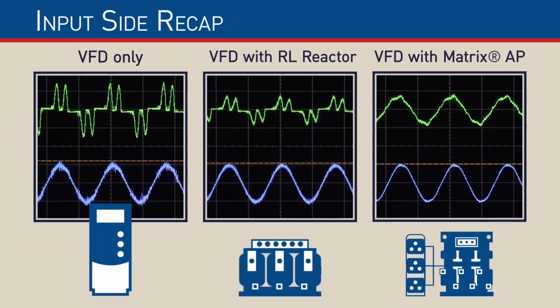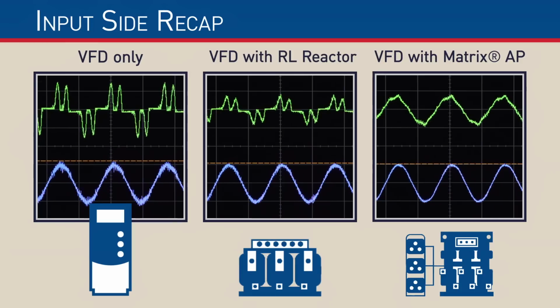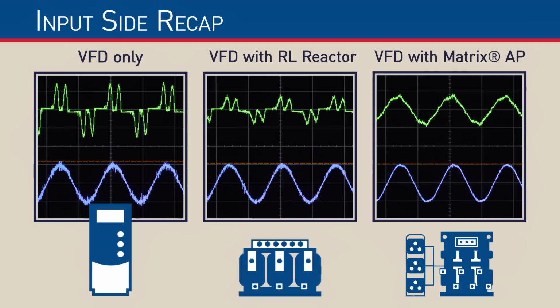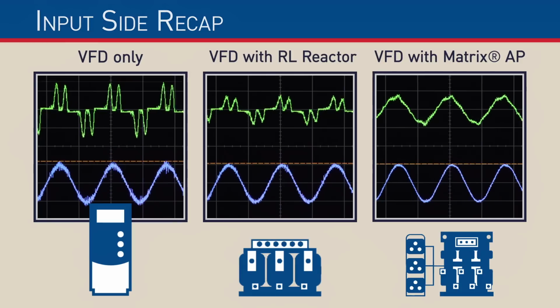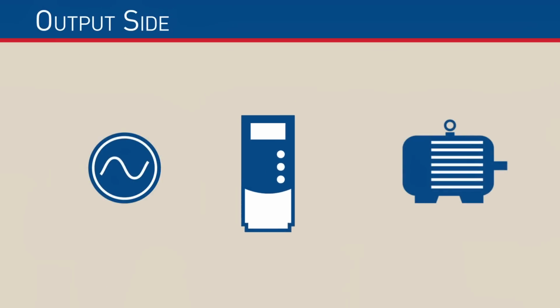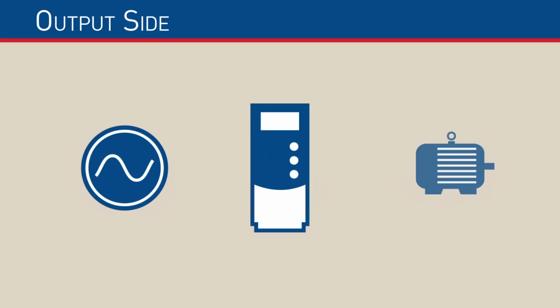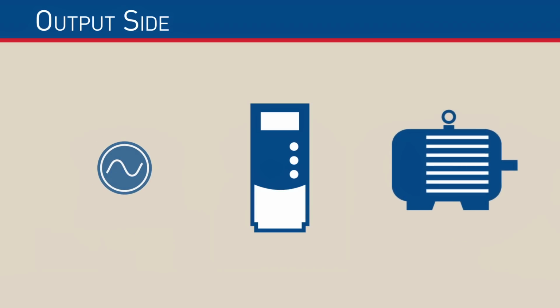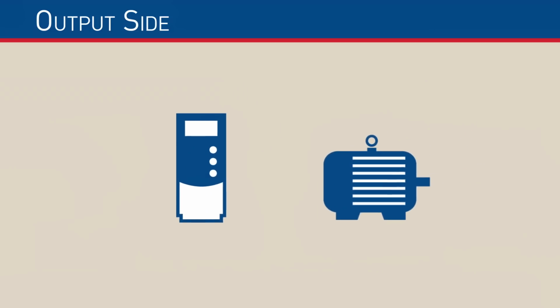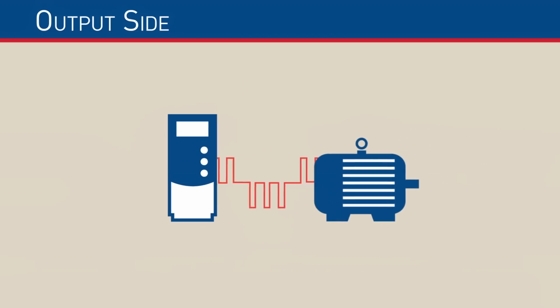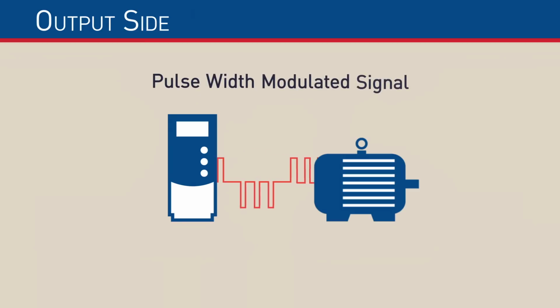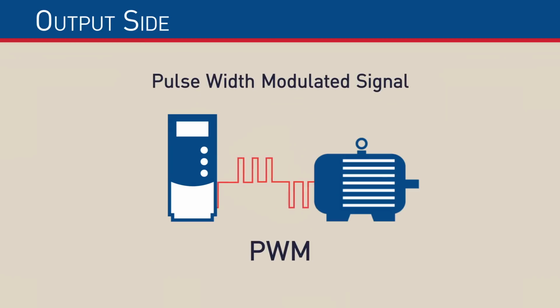It's clear that adding these MTE products at the input side of a VFD will reduce harmonics and help extend the life of equipment. Now that we've seen the effects that a VFD can have on the input side, let's turn our attention to the output side of the drive. Here, we must understand that the drive does not transmit a clean sinusoidal waveform, but rather a series of pulses called a pulse width modulated signal, or PWM, out to the motor.